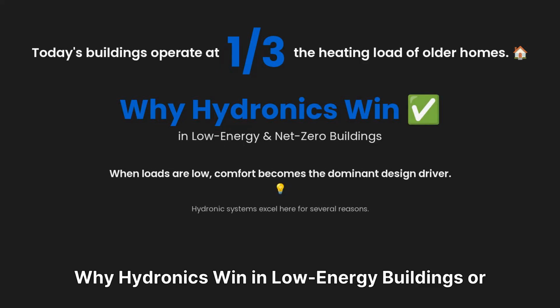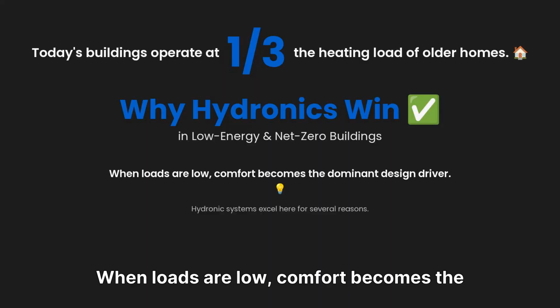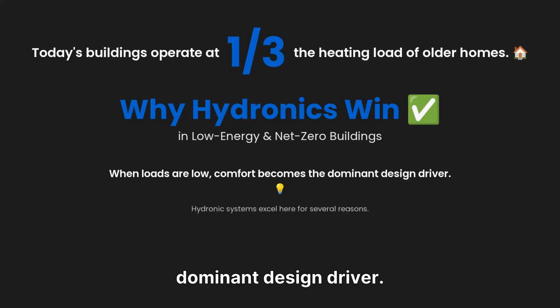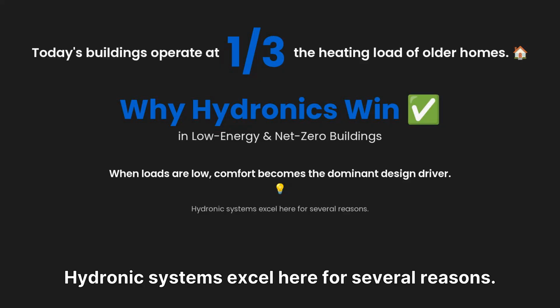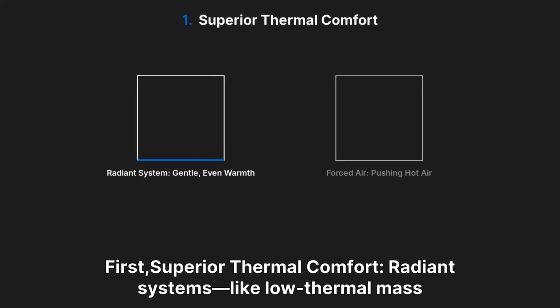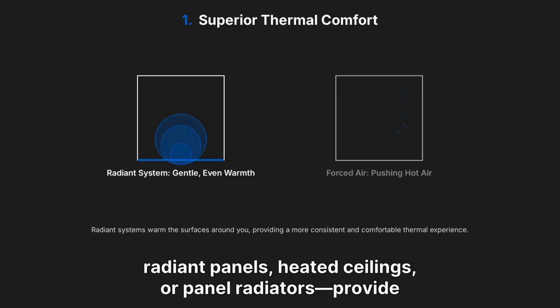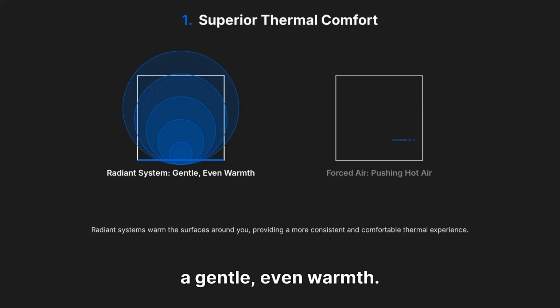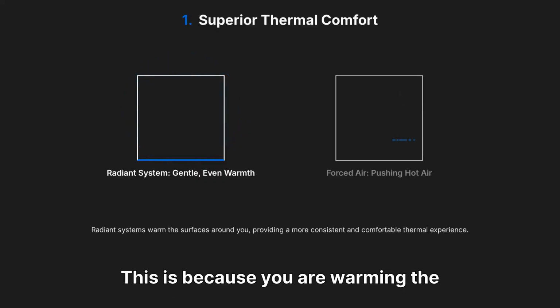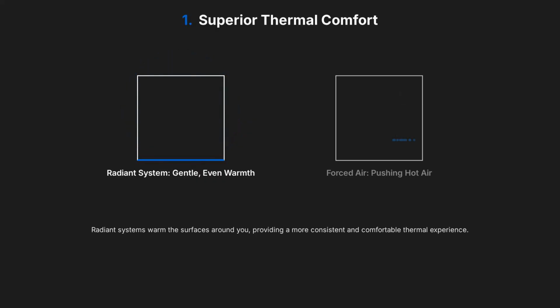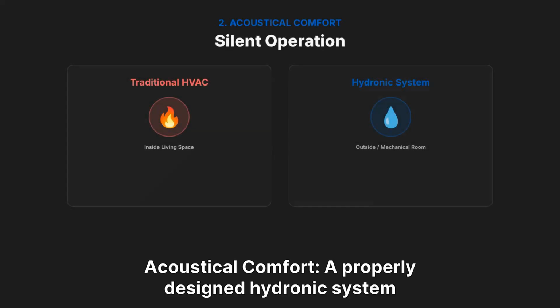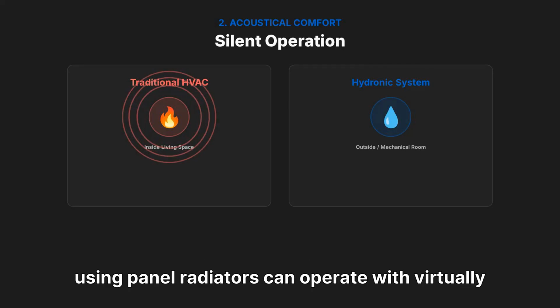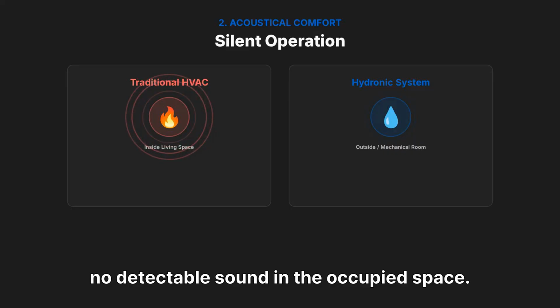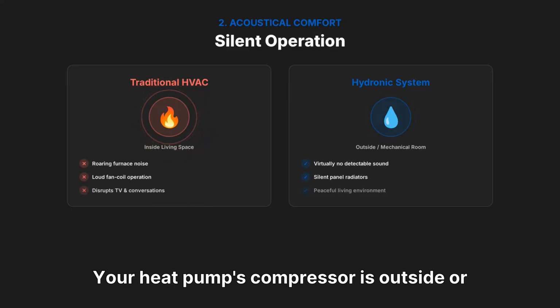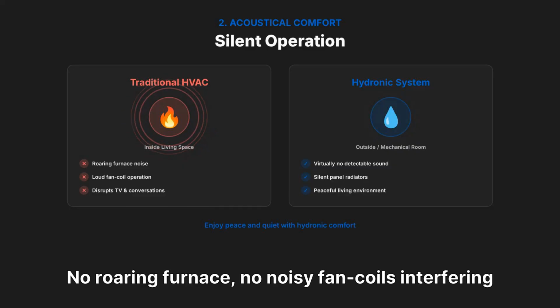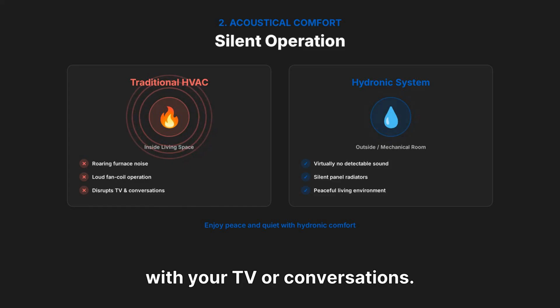Why hydronics in low-energy or net zero buildings? When loads are low, comfort becomes the dominant design driver. Hydronic systems excel here for several reasons. First, superior thermal comfort. Radiant systems, like low thermal mass radiant panels, heated ceilings, or panel radiators, provide a gentle, even warmth. This is because you are warming the surfaces, not just pushing hot air around. Second, acoustical comfort. A properly designed hydronic system using panel radiators can operate with virtually no detectable sound in the occupied space. Your heat pump's compressor is outside or in a mechanical room. No roaring furnace. No noisy fan coils interfering with your TV or conversations.